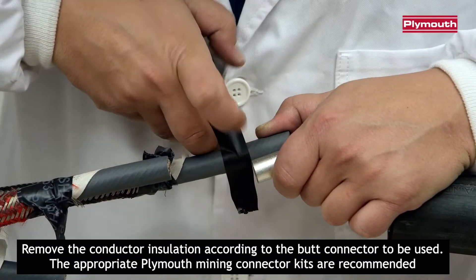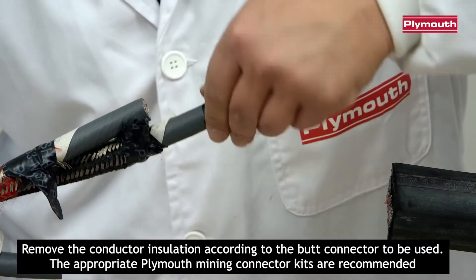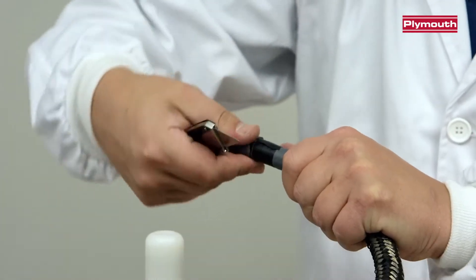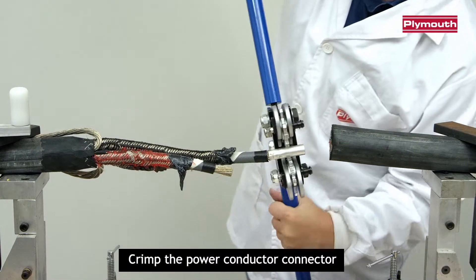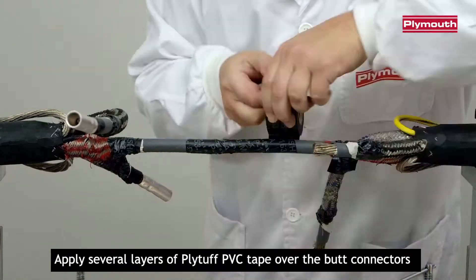Remove the conductor insulation according to the butt connector to be used. The appropriate Plymouth Mining Connector Kits are recommended. Crimp the power conductor connector. Apply several layers of Plytuff PVC Tape over the butt connectors.